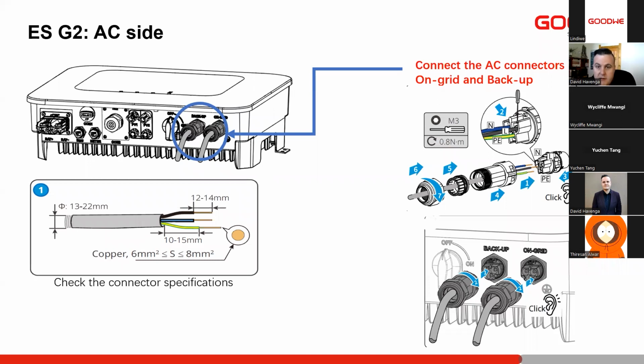You'll see in the user manual, we also do have recommendations for the screw type as well as the torque. If you want to make sure you are installing it and crimping your cable sufficiently, you can use a screwdriver with a torque setting.